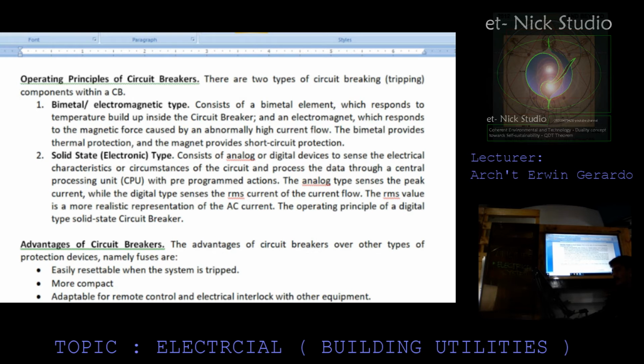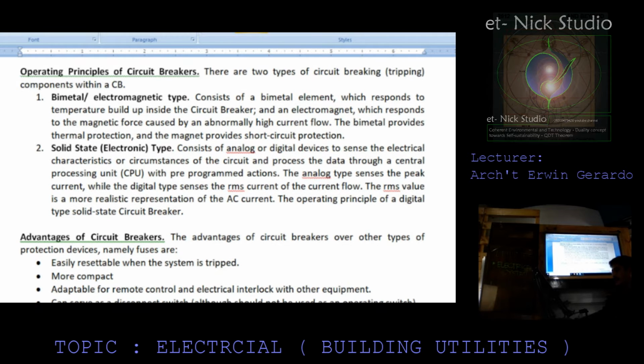Operating principles of circuit breaker. There are two types of tripping components within a circuit breaker. Number one is the bimetal or electromagnetic type. It consists of a bimetal element which responds to temperature buildup inside the circuit breaker, and an electromagnet which responds to the magnetic force caused by an abnormally high current flow. The bimetal provides thermal protection and the magnet provides circuit protection.